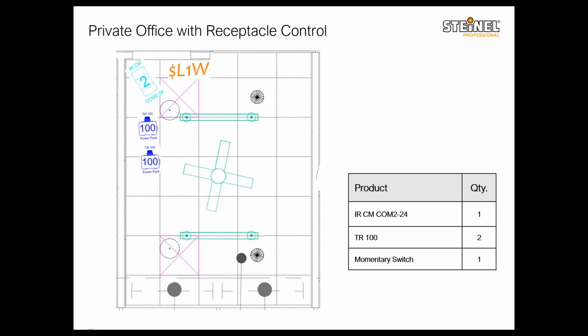Again, as you can see, small office load, and the same scenario, since the topic of ceiling fans came up. So same combination and same products can be used to control that ceiling fan based on occupancy as well. So if you don't have receptacle control, let's say in this office, but you want the ceiling fan to be controlled through occupancy, you just need this combination. An IR corner mount COM2-24 sensor, two TR100 power packs, and a momentary switch to control the lighting. You can use a slide dimmer in place of the momentary switch as well if you have dimming in such a small office. Of course, nowadays dimming is becoming quite popular. So yeah, slide dimmer in place of that momentary switch, and you have, again, all the things you need in a small office.